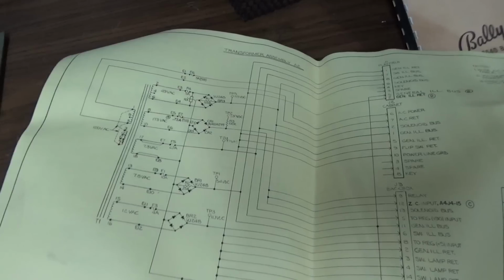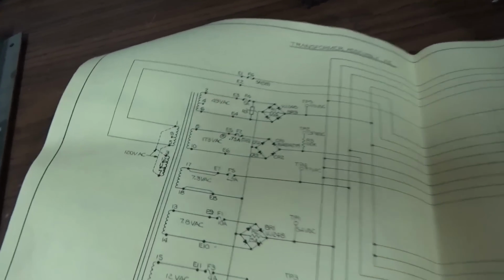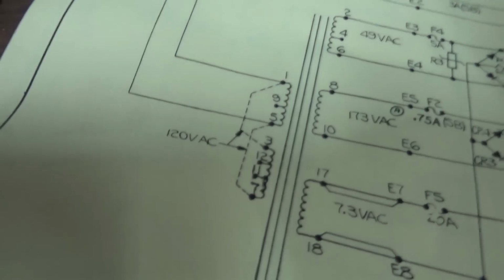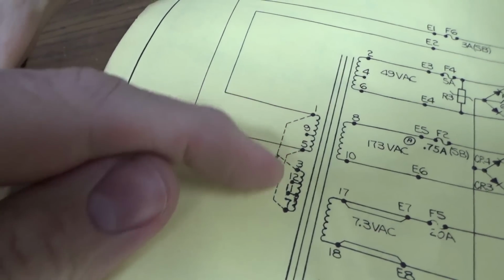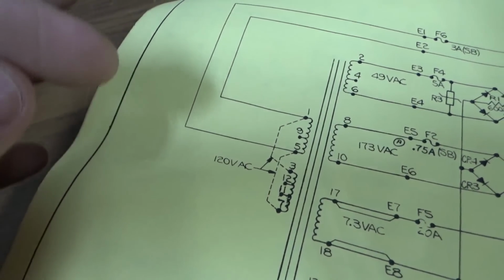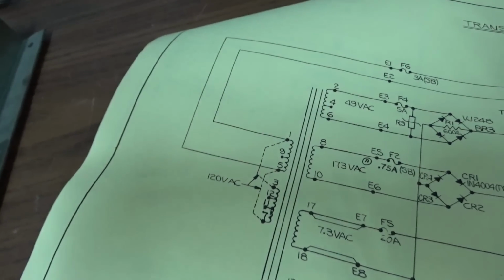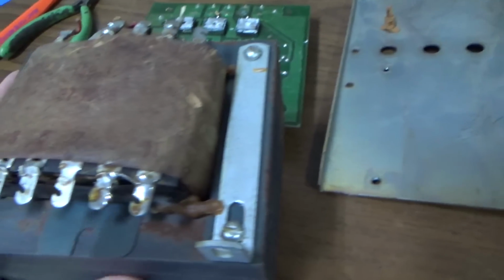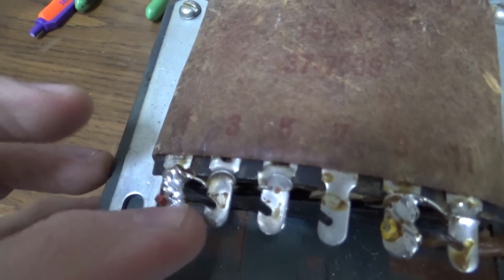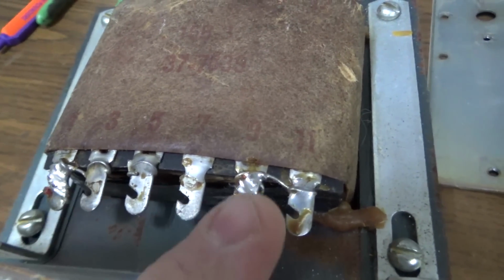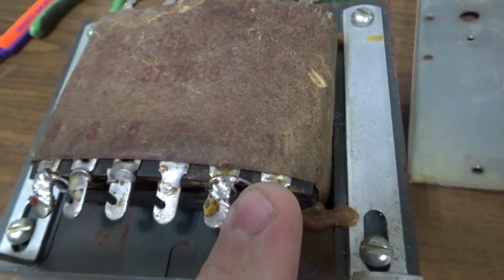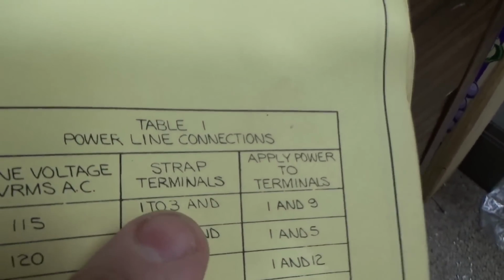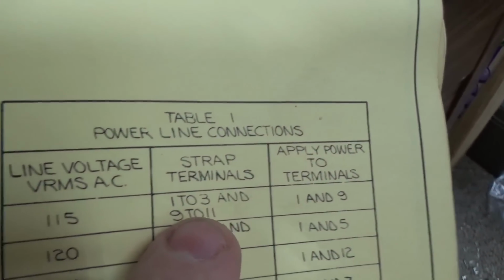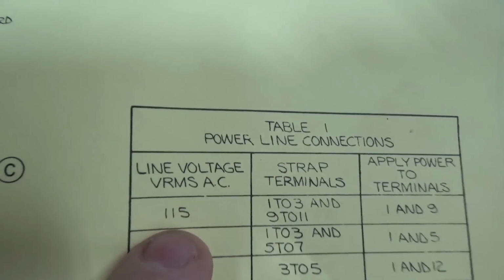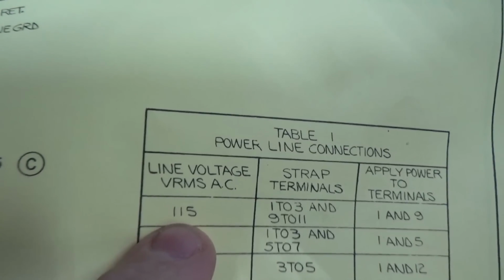The first thing we're going to do is look at the set of jumpers on the input of the transformer that changes the input line voltage. If you look, this one has 1 and 3 connected, and 9 and 11 connected — that means it's set up for 115 volt wall line voltage.